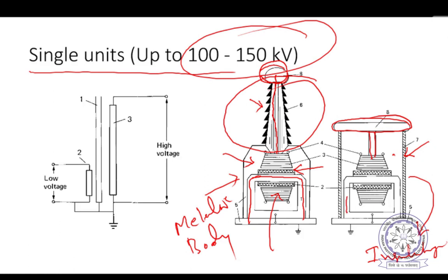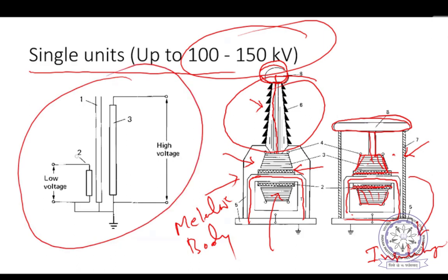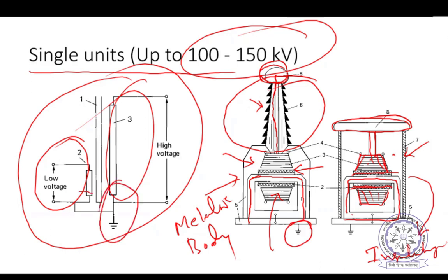Here also one single core is there, and on that the primary circuit, and above that the secondary winding. The trapezoidal type of winding arrangement is to ensure equal distribution among the winding layers in transient conditions. For that purpose, these windings are made trapezoidal, not simply cylindrical. The cross section looks trapezoidal. Now here we have a representation of the same thing with a primary here and then the secondary here. This is how single units up to 100 to 150 kilovolts are designed. You can see the core is at ground potential, and one winding of the primary is also at ground potential. So these are the designs for up to 150 kilovolts.